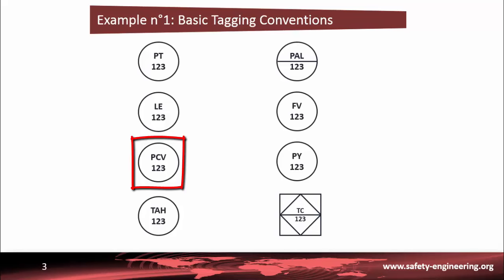PCV means a control valve which regulates pressure. The first letter is P for pressure. Because there is no line inside the circle, all these devices are located somewhere in the field, probably close to the general area shown on the P&ID.